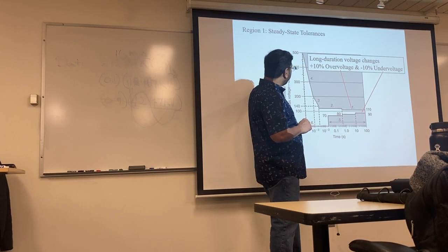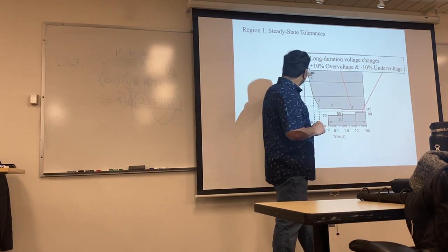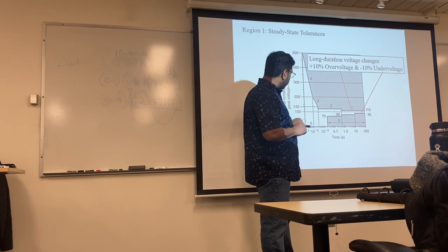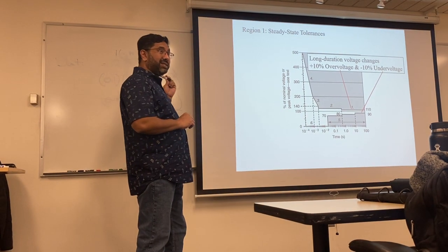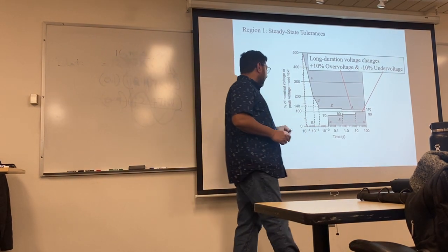If I'm going like 400% high, there's no way I can sustain it for 10 seconds. In fact, 400% somewhere here, so that's less than 1 millisecond. And we were talking about 16 milliseconds, so in that case, it's gone. Don't even think about it.